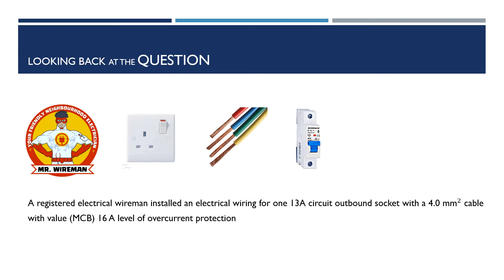Looking back at the question, a registered electrical wireman installed electrical wiring for a 13 ampere circuit outlet socket with a 4 mm square cable with MCB of 16 ampere level of overcurrent protection in a shop house with single phase supply entry. Now, what is the fault and how to correct it? The answer is the cable.